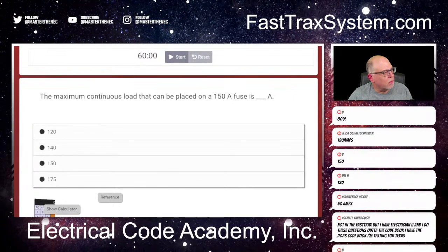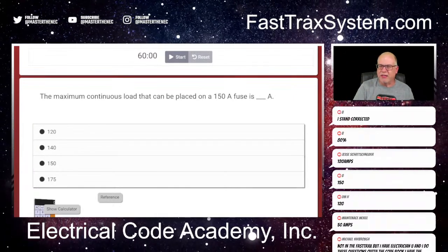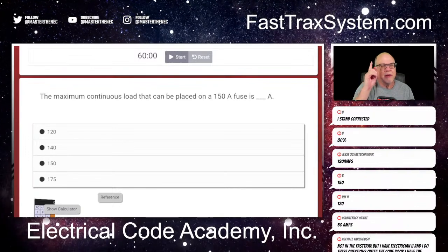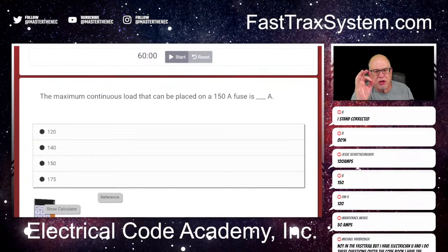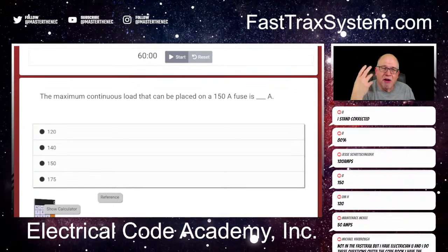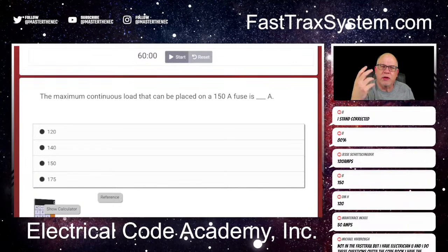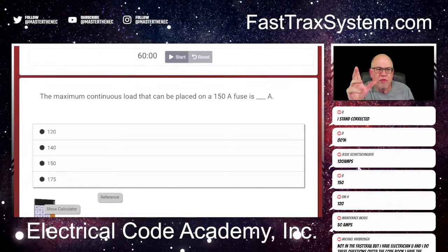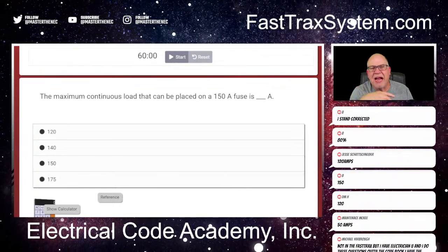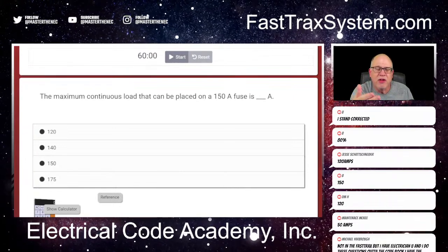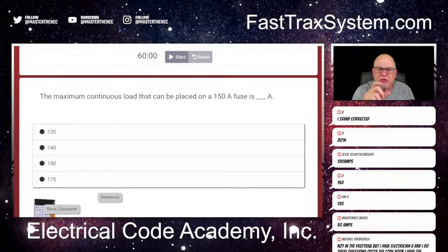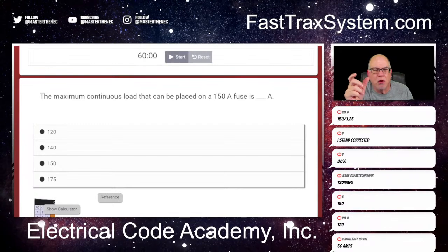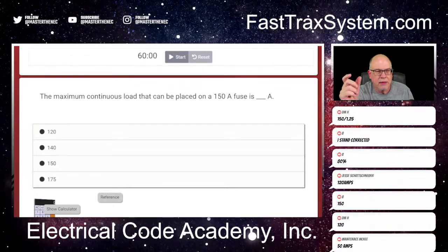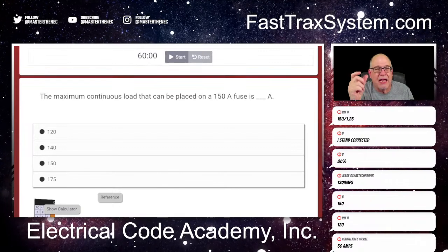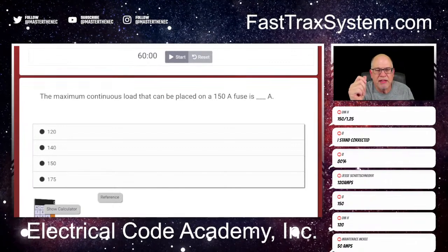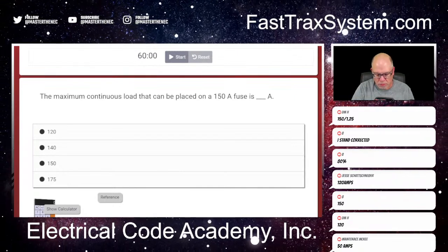It's not going to be all these other numbers in here. It's not going to make any sense to be 140, 150, or 175, because remember, continuous loads, if you're talking about the conductor, or you are given an actual load, then you take it at 125%, right? If it's the overcurrent device, and that's what they give you, and they want to know what's the maximum continuous load that you can put on that device, remember that 80% is the reciprocal of 125. So I can take the rating on the overcurrent device, right? And do that 125, do it by 80%. Then that would give me the answer, okay?